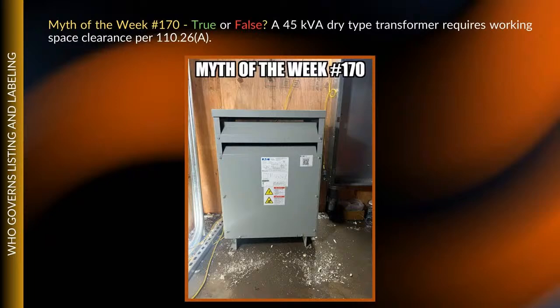110.26A is for working energized. How do you work energized safely? Well, you follow NFPA 70E, right? NFPA 70E tells you what to do when you cannot shut it off, or when you're in the process of shutting it off. It tells you how to dress, how to lockout/tag out, how to verify absence of voltage—all of it.